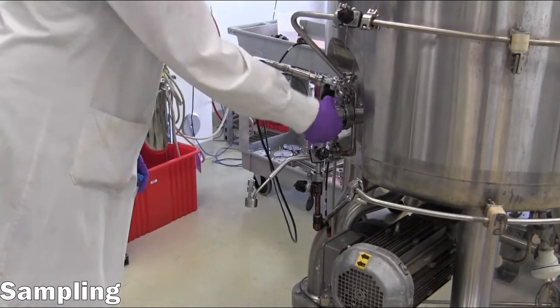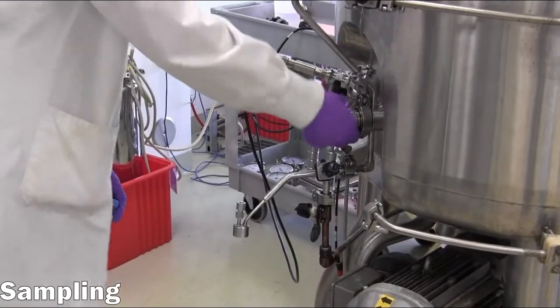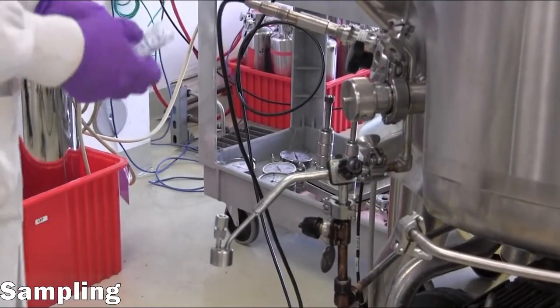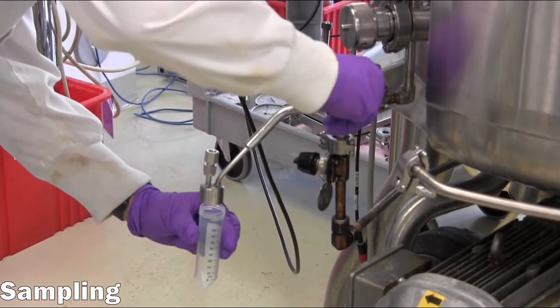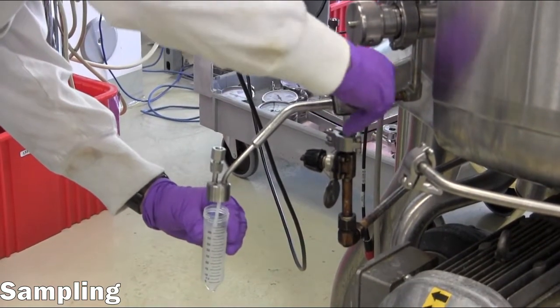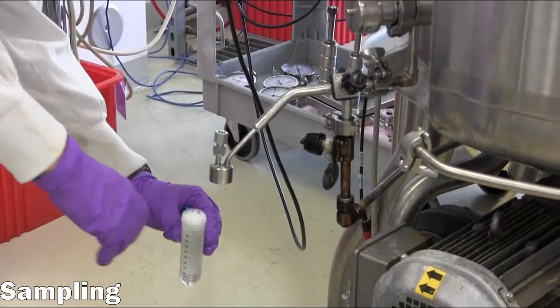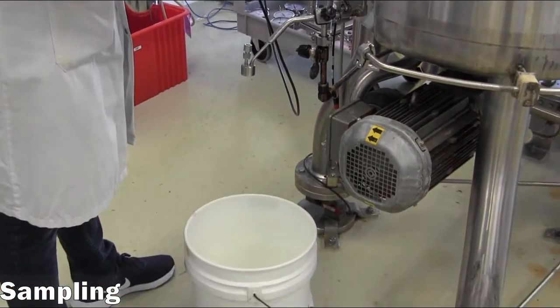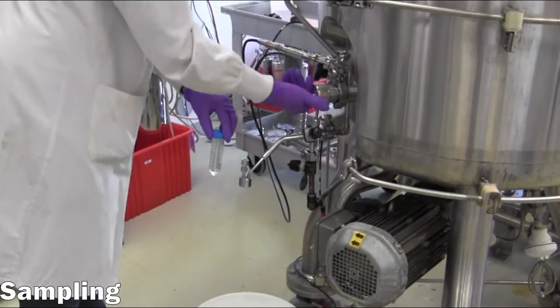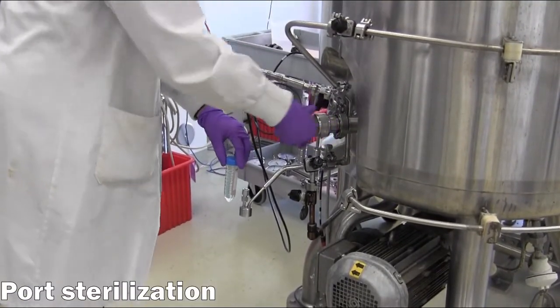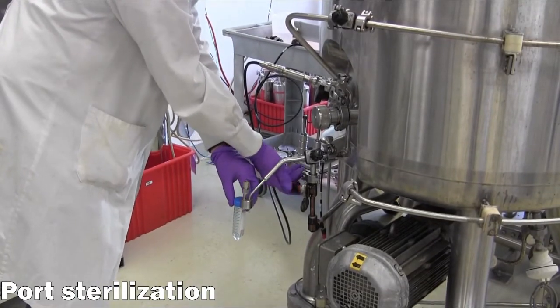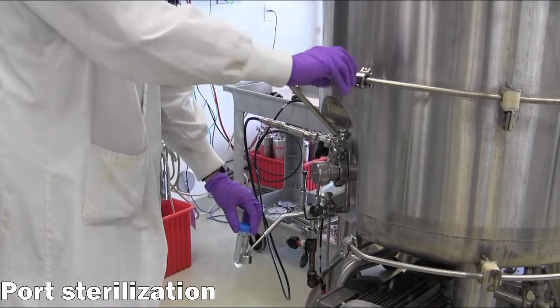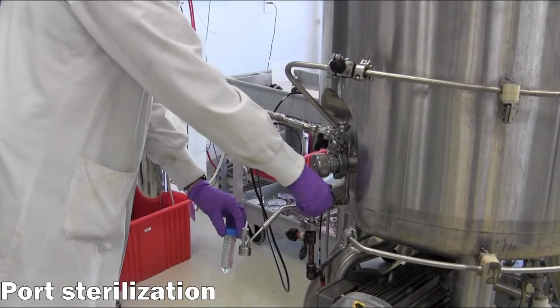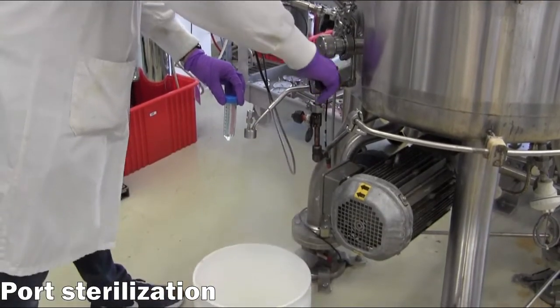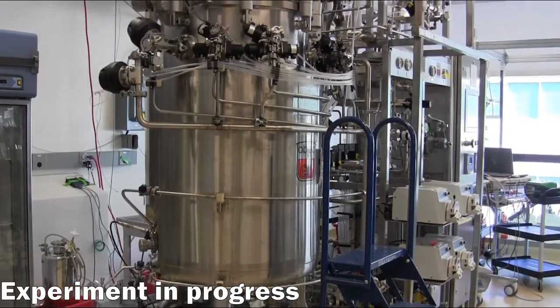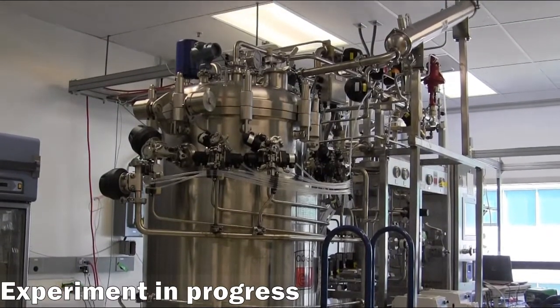To collect a sample, open the sample port valve on the reactor, followed by the hand valve on the sample assembly. Collect as much sample as is outlined in the experiment sampling procedure, then close the hand valve, followed by the reactor valve. Sterilize the port by opening the steam line hand valves above and below the sample port. Open the hand valve momentarily to clear the line and steam the outlet. The experiment is in progress and continues until the end of fermentation.